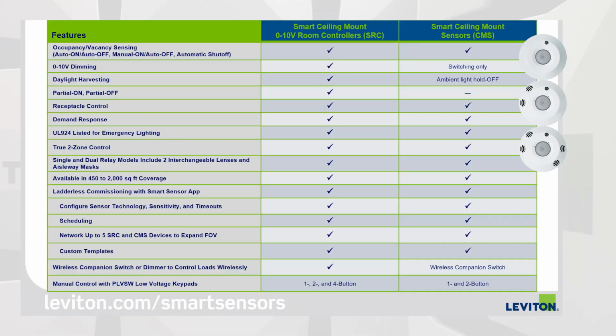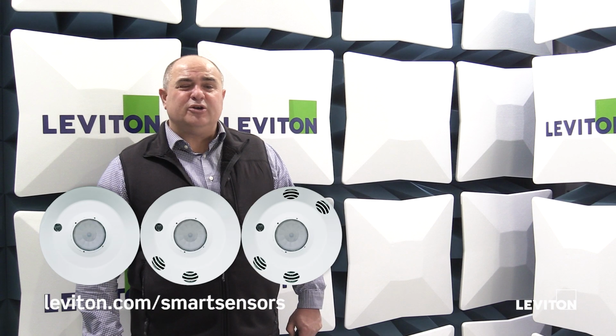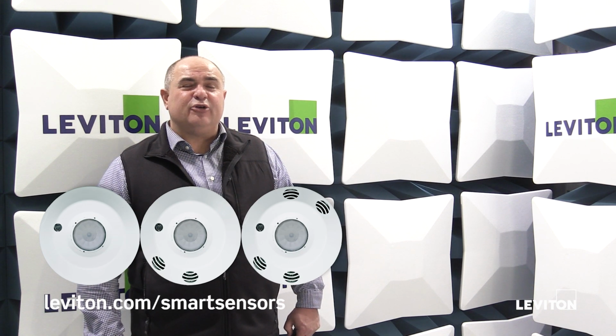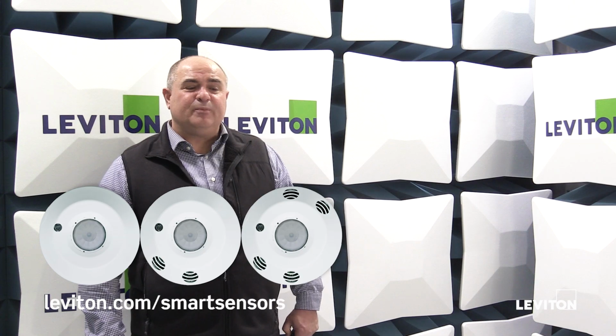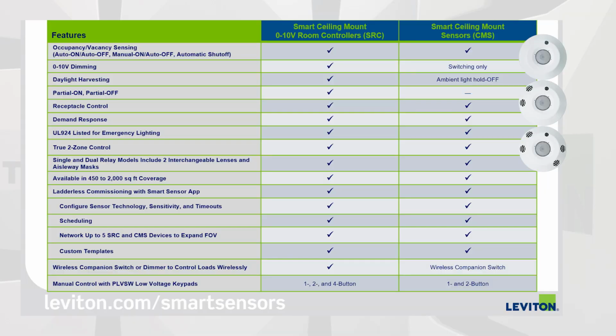And one of the things that allows this to be used in areas all the way up to 10,000 square feet is that both of these solutions can be paired or networked with up to 5 units together. So 5 smart room controller solutions or 5 smart ceiling mounted sensors can be grouped together to expand the field of view.